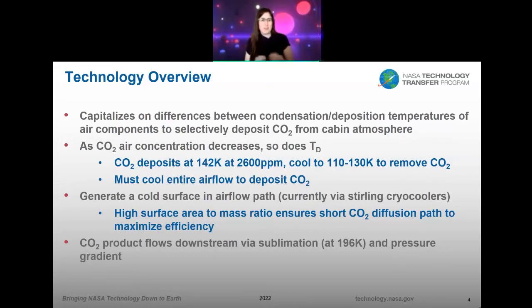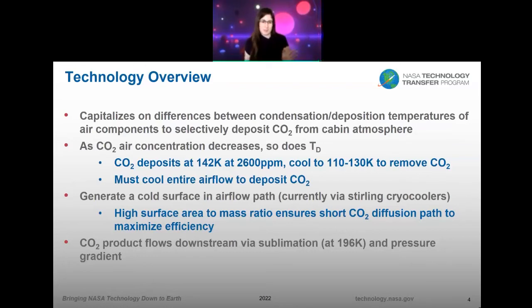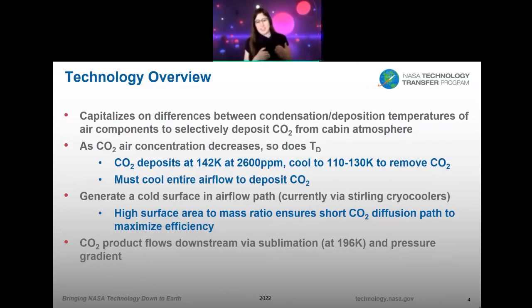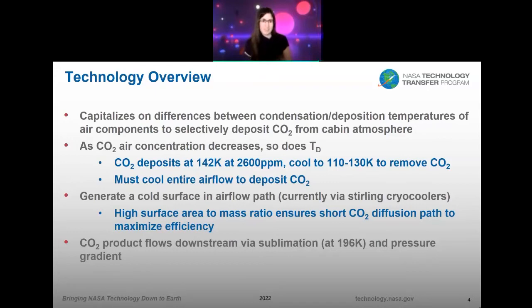So how do we cool the CO2 out of the air? We generate a cold surface in the airflow path. We're currently using Stirling cryocoolers specifically, because these are readily available in Earth applications. You would potentially do it different ways in space, but cryocoolers work everywhere. To generate a cold surface, you need a high surface area to mass ratio to ensure the CO2 diffusion path is as short as possible so you collect CO2 as efficiently as possible. The design of your cold surface factors in just as much as your source of cooling. Once you collect your CO2, your system fills up. You have to regenerate the system and get your CO2 product out for conversion into useful products or storage downstream. We turn off our system, start to warm it up, and pure CO2 sublimates at about 196 kelvin. If you want to increase the pressure further, you just increase the temperature to what you need.